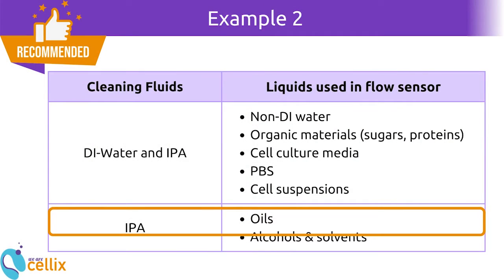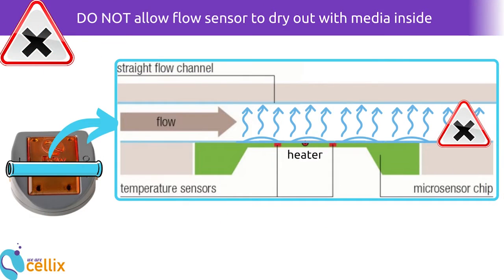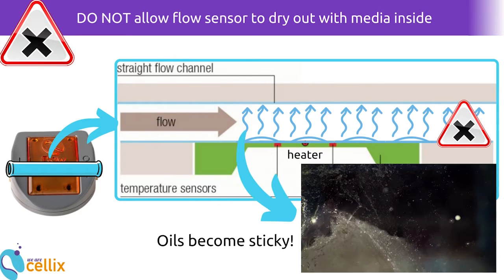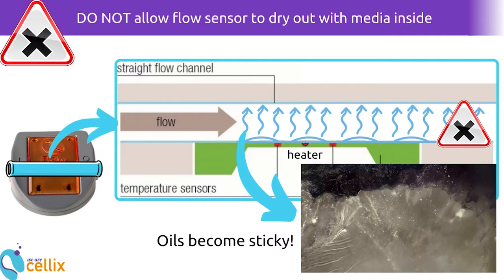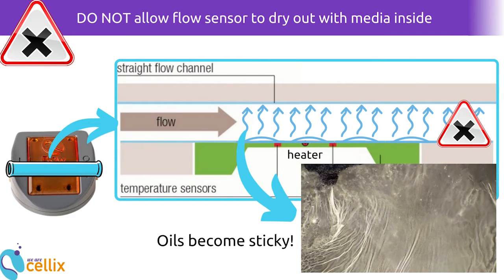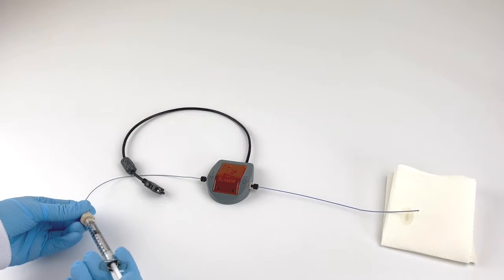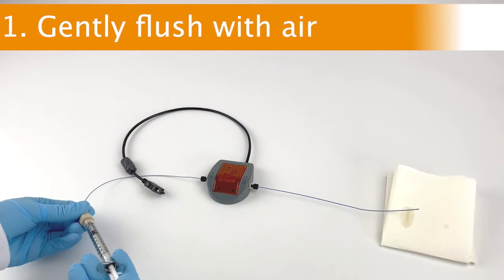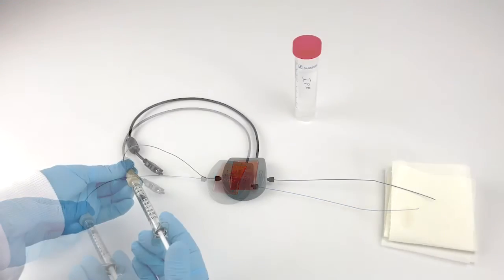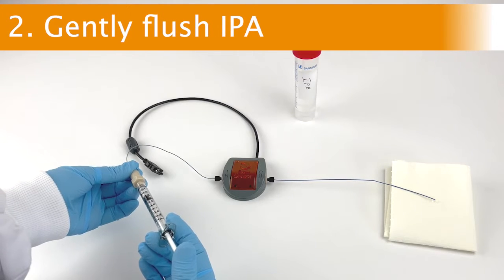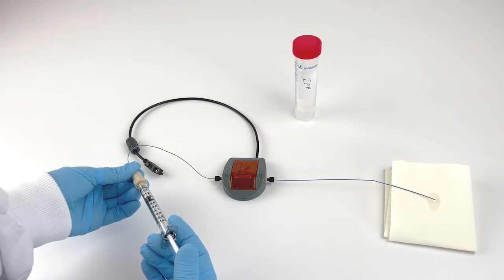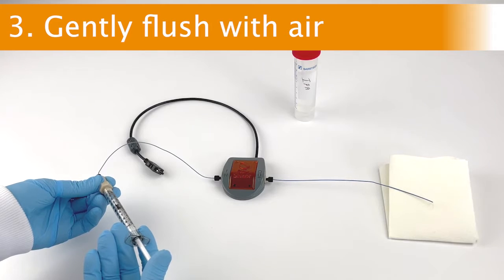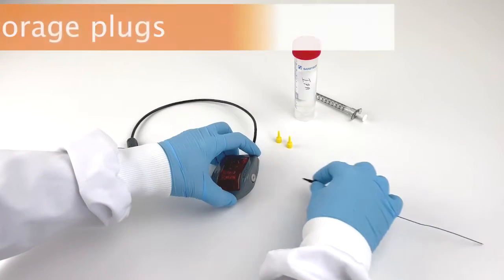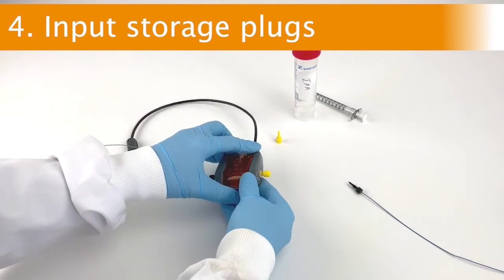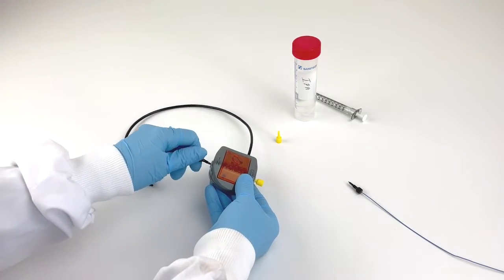Example 2. Working with oils. Do not allow the flow sensor to dry out with residual liquid media inside the flow channel. Oils can leave sticky films on the wall of the flow channel and are difficult to remove. The cleaning protocol is as follows. 1. Gently flush with air. 2. Gently flush with solvent such as IPA. 3. Gently flush with air again. 4. Close the input and output ports to the flow sensor with the plugs provided and store.